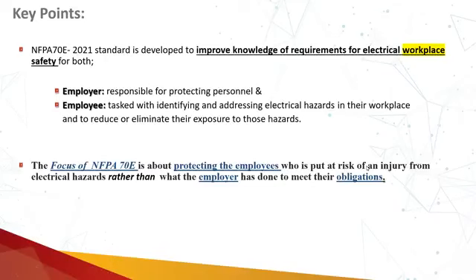Okay, so the focus of NFPA 70E is about protecting the employees who are put at risk of an injury from electrical hazard, rather than what the employer has done to meet their obligation. In the exam, the questions will be like this: that 70E is adopted by employers to fulfill OSHA obligations. So this answer is not correct. The employers are adopting NFPA 70E for protecting employees only. It's not a mandatory requirement of OSHA that you have to adopt 70E requirements.